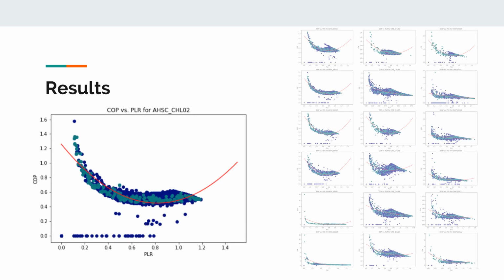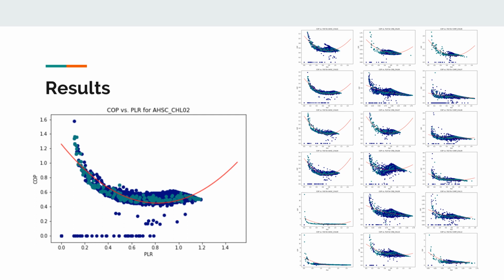Now we will discuss the results from the project. First, we highlight the second-order regressions between the coefficient of performance and PLR. On the left is a plot of the regression for one chiller, in this case, AHSC Chiller 2. On the right is a plot that contains a regression for all 18 of the applicable chillers. It is known that these two features of chillers generally share an approximately quadratic relationship. Because of the nature of how central facilities typically runs equipment, much of the data was concentrated in the PLR range between 0.5 and 1.